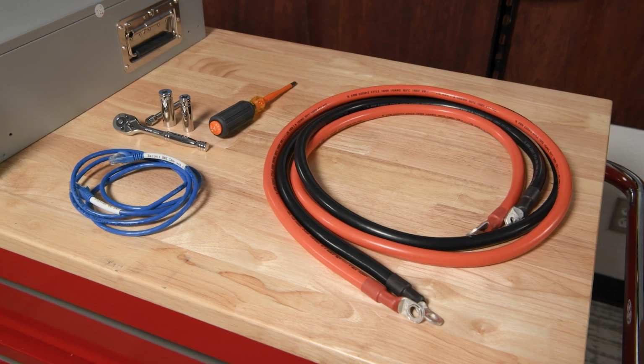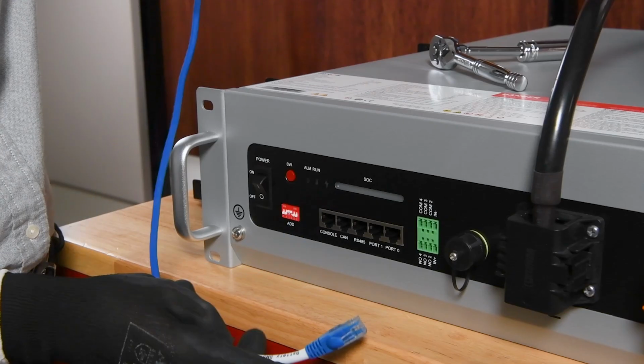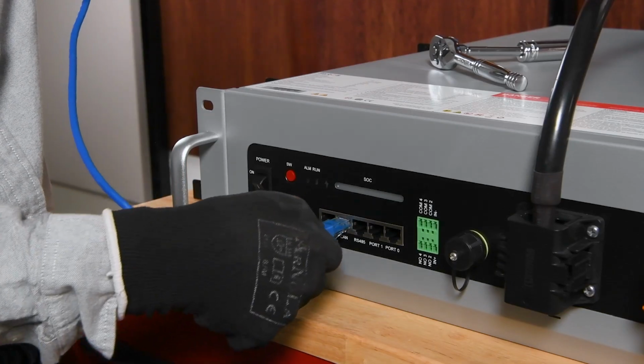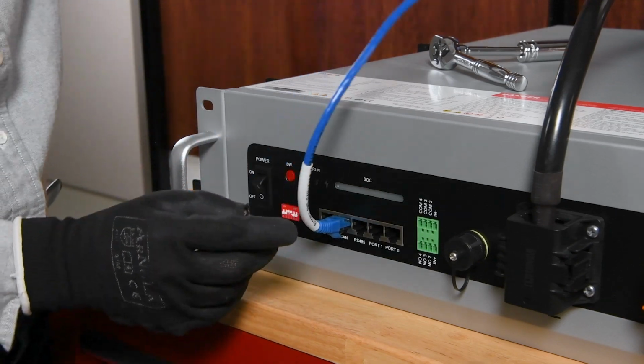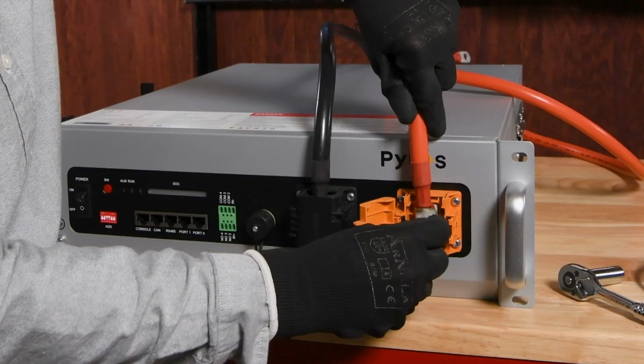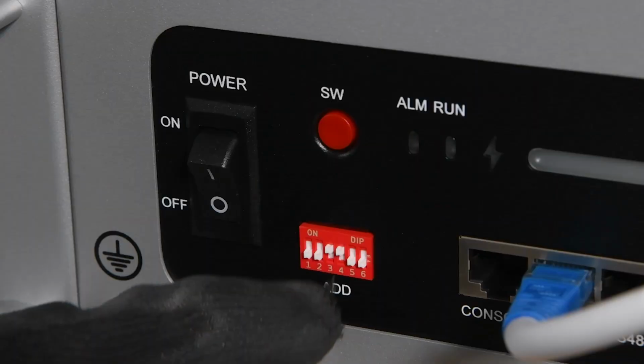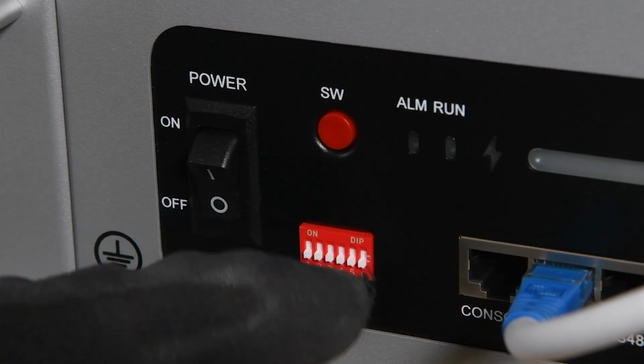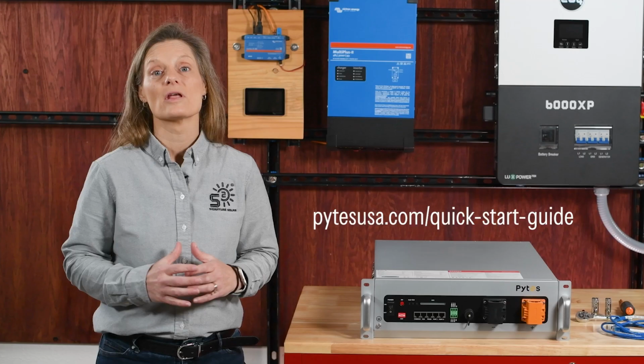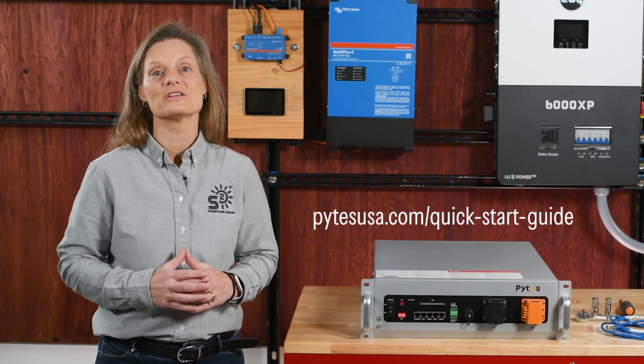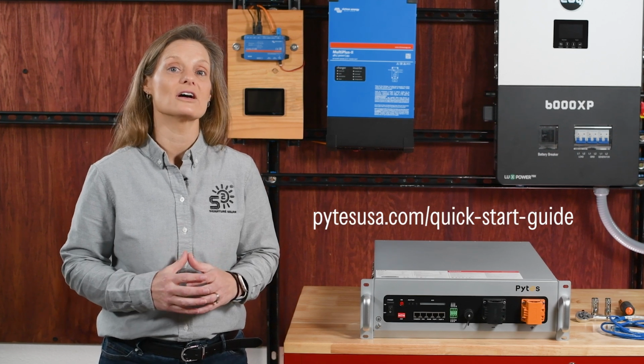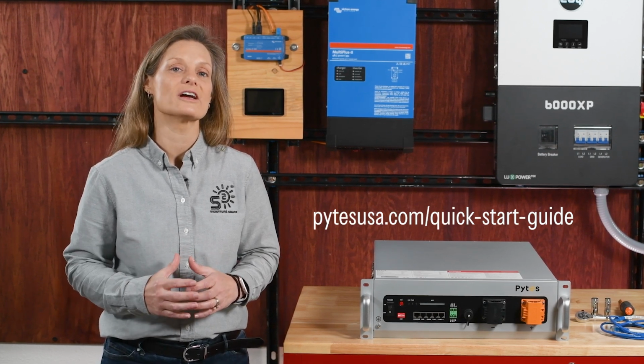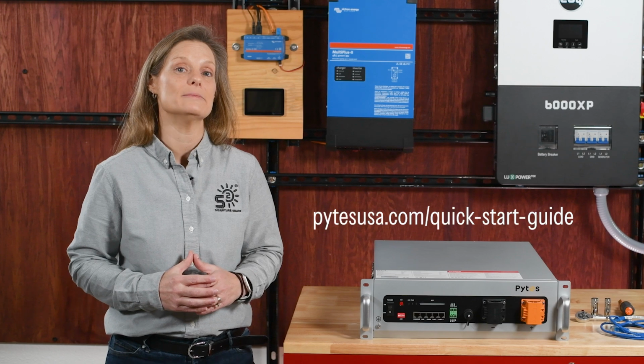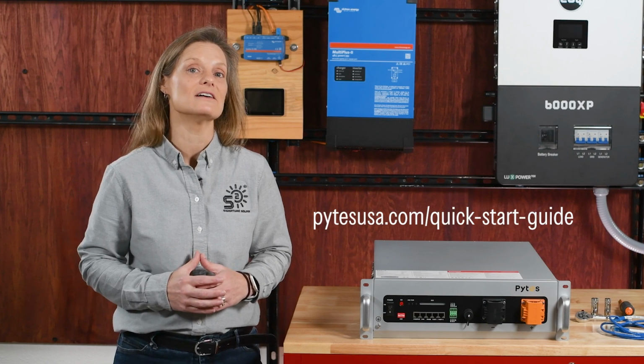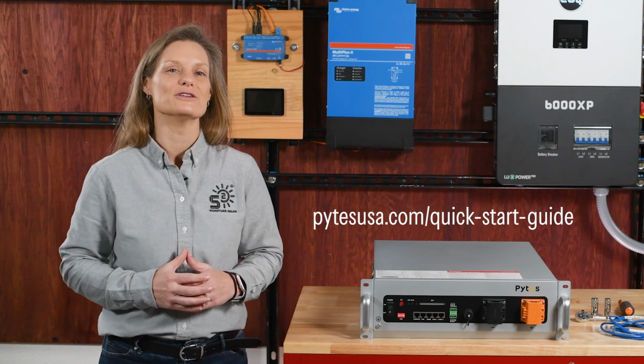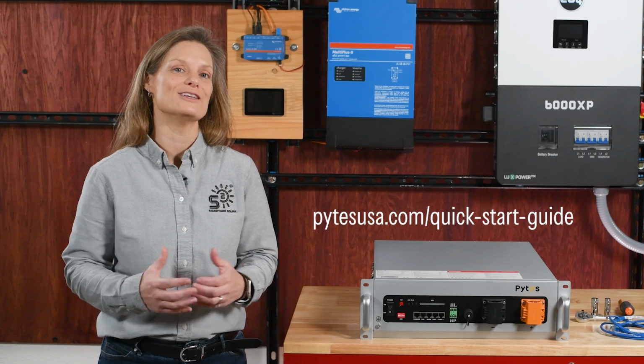It's important to check that the communication cable has the correct pinouts before beginning, as the setup is precise. For Victron systems, the communication protocol requires that all dip switches are set to the down position. Always refer to the Pytes Quick Start Guide at pytesusa.com/Quick Start Guide to verify the correct dip switch settings and pinout details specific to your inverter. We'll put this link in the description.